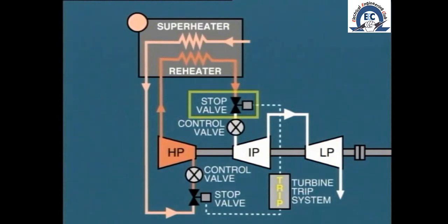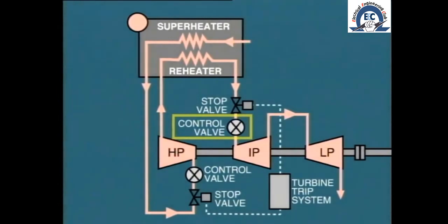Similarly, the reheat intercept valve is fitted to assist in precise control. The intercept valve is, in fact, a control valve that normally remains wide open, allowing steam flow from the main steam control valves.